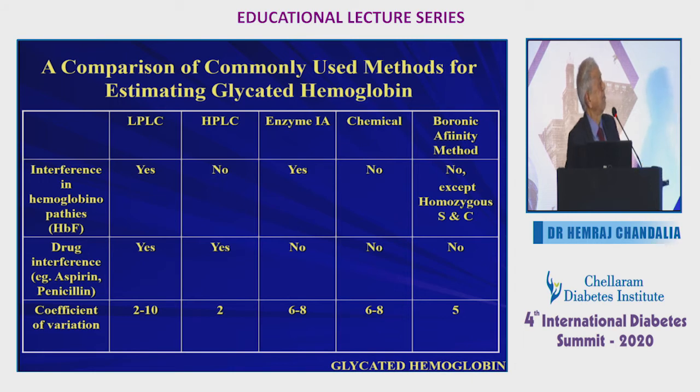As a laboratory method, hemoglobin A1C, the coefficient of variation is very, very low. In fact, with most good machines, it's 2 to 3%. I must tell you that blood glucose does not have as much accuracy as A1C has nowadays. See, blood glucose is now considered a more unreliable analyte in the laboratory because glycolysis can proceed in spite of your using a fluoride bulb.